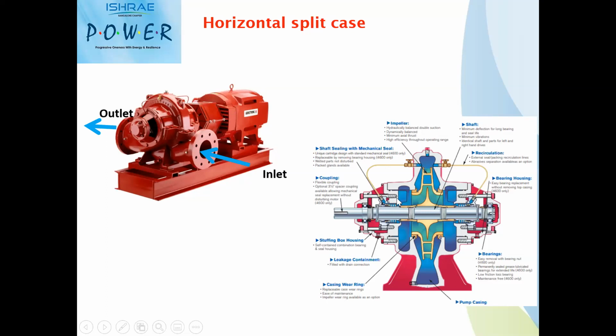As for construction, in end suction pumps the shaft was cantilever, whereas here the impeller is mounted on a two-sided supported pump shaft. So it will have two bearings and two mechanical seals. These are the mechanical seals. These are the two bearings on which the impeller is mounted. The advantage of this pump is that it always has a double suction impeller, which gives better efficiency in terms of performance. The disadvantage is that it has two mechanical seals and two bearings on the pump alone, and additionally it will have bearings on the motor side as well. So maintenance wise, it is a very heavy pump, and if you want to maintain these pumps, you need to completely open the casing and access the internal parts of the pump.